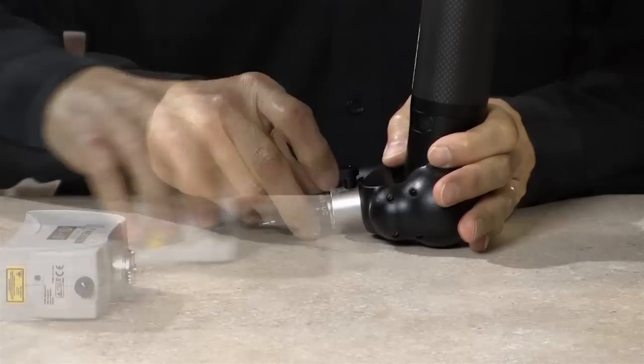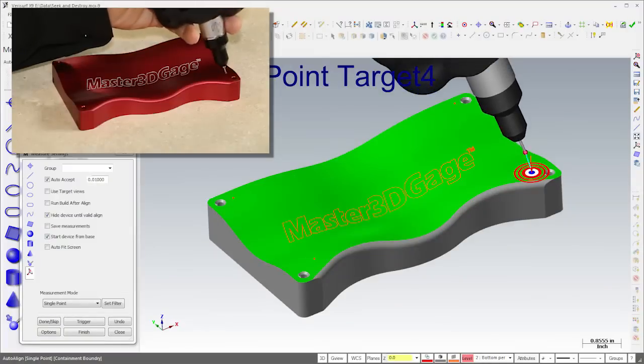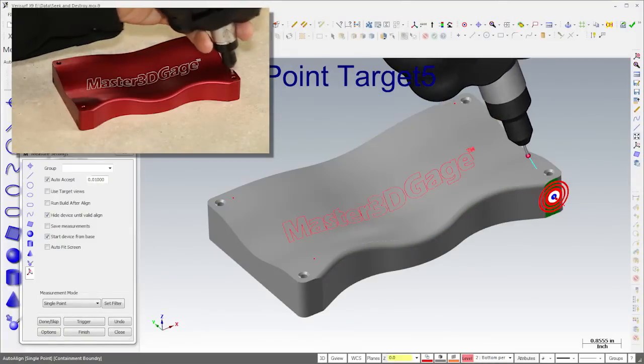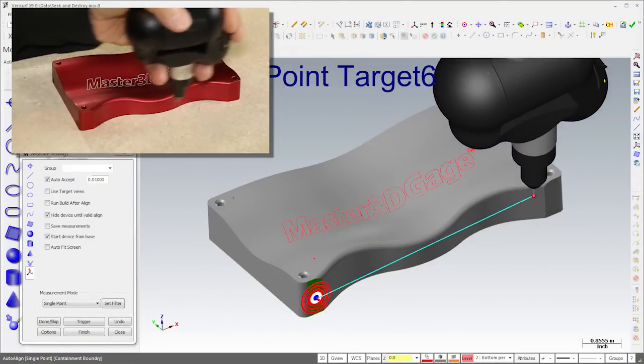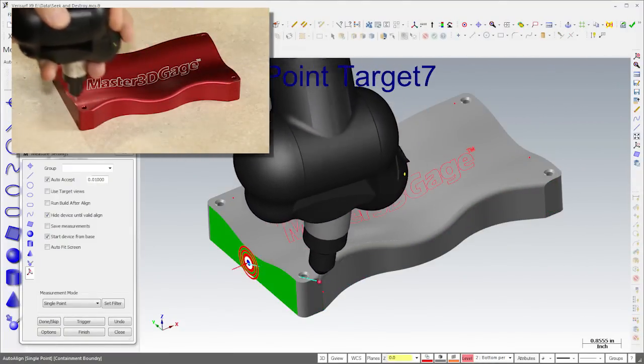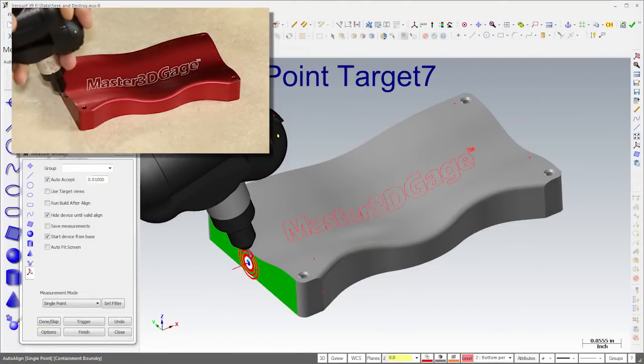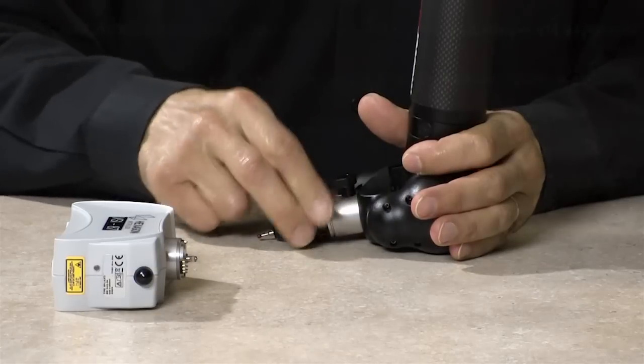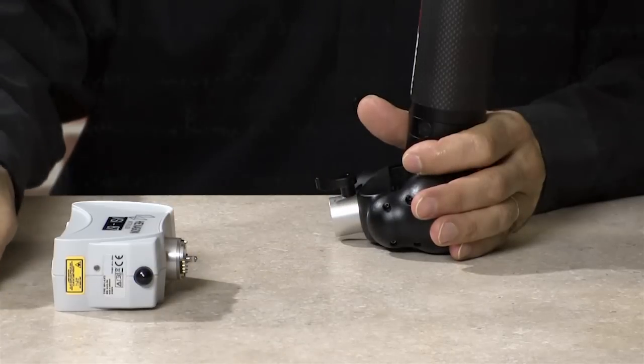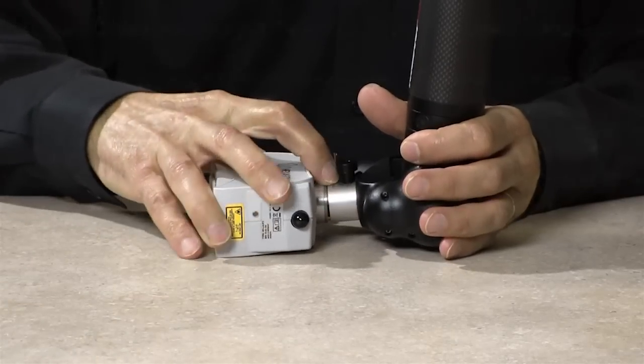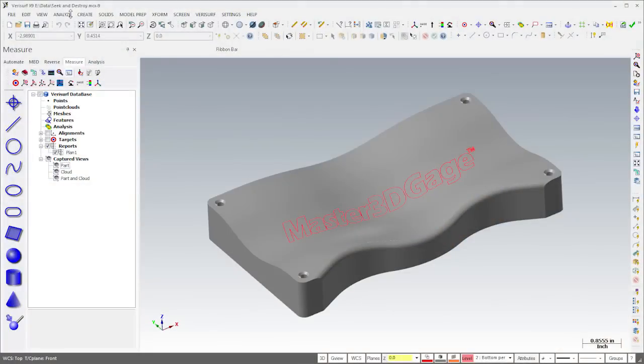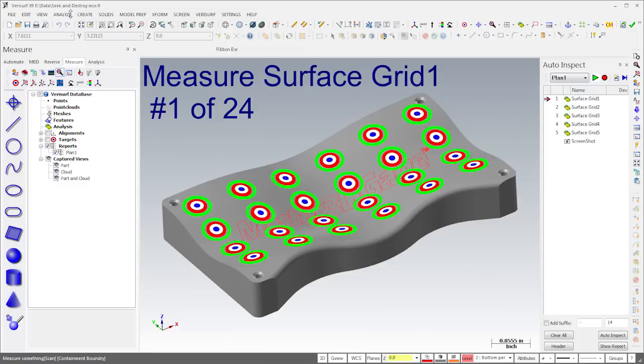I'll hot-swap the scanner for the probe and then align the Master 3D gauge using Auto-Align. When the alignment is complete, I'll hot-swap the probe for the scanner. The repeatable mount allows me to switch between probes without having to recalibrate. I'll then open Auto-Inspect and run the inspection plan.